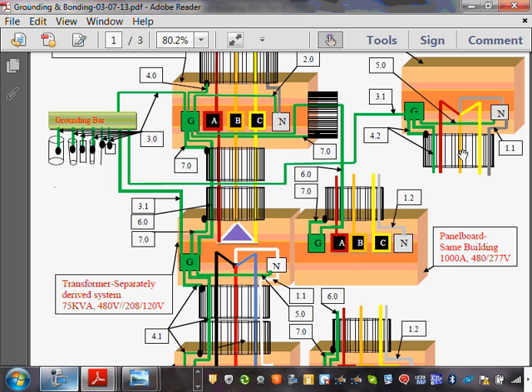Anybody, am I missing anything? Yes. On the last job that I was on, we didn't need a neutral in the building, it was 480 wye. We bonded it there because the generator needed to be bonded, but we didn't take a neutral in the building. Oh, we're not utilizing the neutral. Right. But did we bring it to the first disconnecting means and bond it? The generator circuit breaker was there. Yeah, in the generator. That's your first disconnecting means. You're not utilizing the neutral. Yeah, if you're not utilizing the neutral. Sorry, thank you, Jeff.